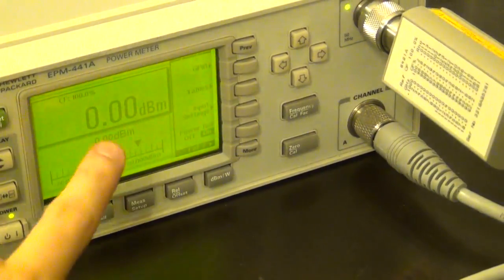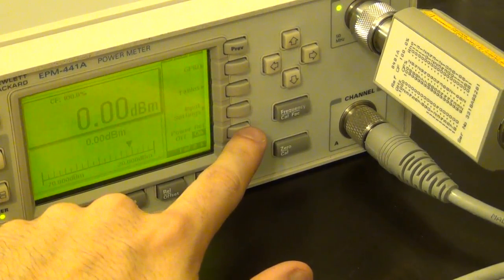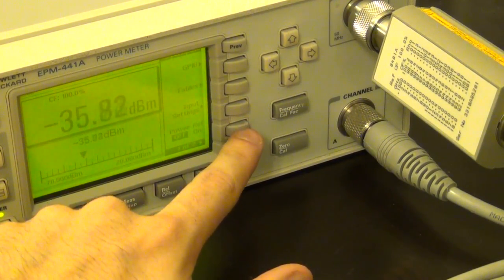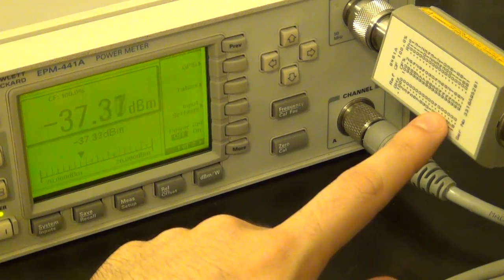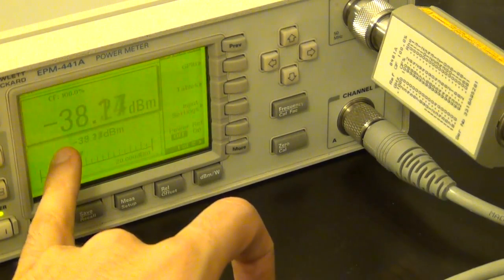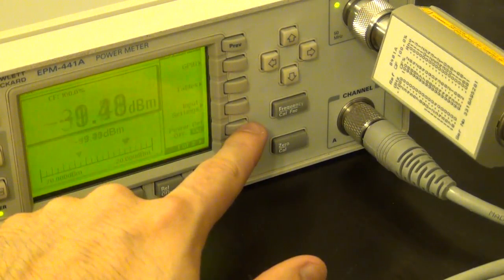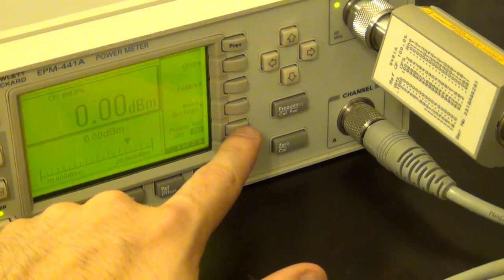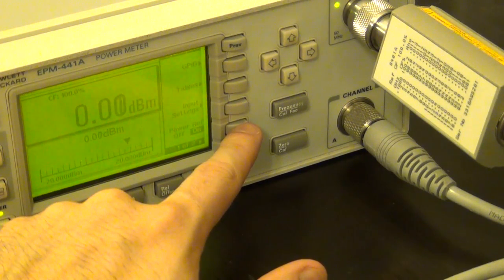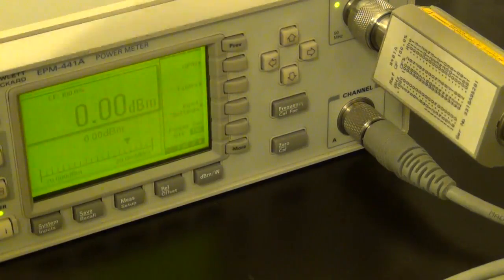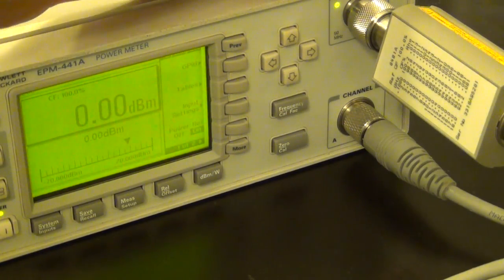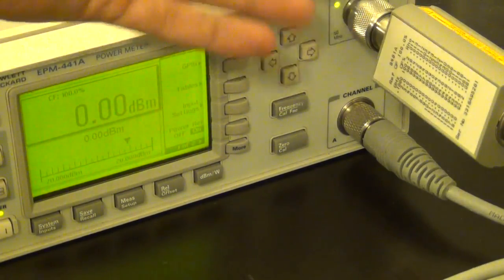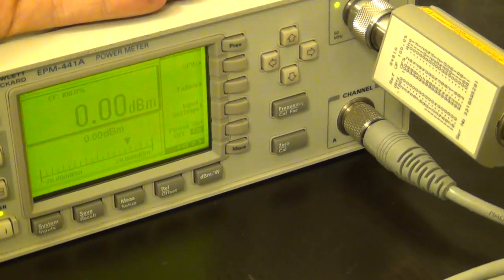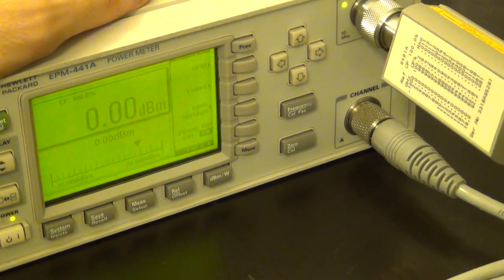So you can see now it says 0 dB, and if I go ahead and turn the power cal off, it's going to go to the noise floor. This is a minus 30 dB noise floor part, so you can see it's just below that. If I turn it back on, it should go back exactly to 0. Now, what is really important to note is that, like I was saying, if the reference calibration power is not 0 dBm, then it's going to assume that it is, and it's just comparing it versus itself. That's why it says 0. It doesn't mean it is correct.